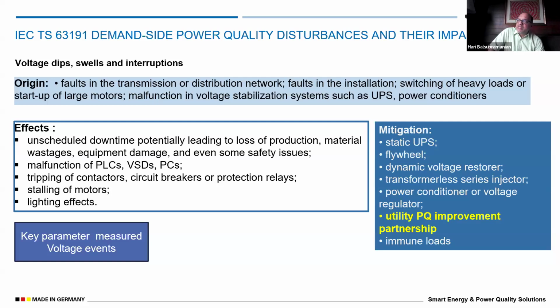Unscheduled downtime is the effect, because suddenly something happens and the PLC trips. Sensitive VFDs in pharma companies can suddenly trip, stating low voltage. But when we go to the multifunction meter, it says it is always 230 volts. We come back and tell them there is no voltage drop, but it could have happened within 20 milliseconds or 10 milliseconds, which your normal multifunction meter cannot sense. Then we have tripping of contactors. When the power to the coil of the contactor is lost for a certain time, it naturally releases the contact. Then you have stalling of motors, and lightning can also cause voltage sags and swells.